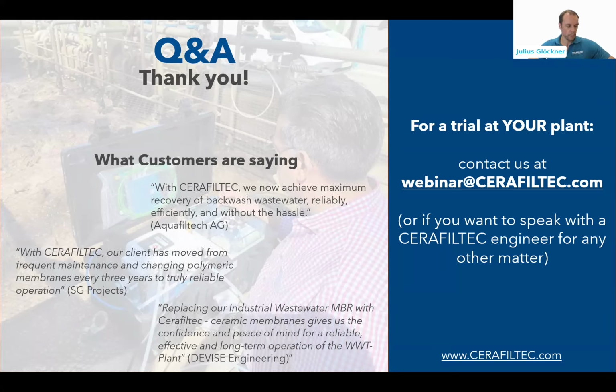I'm sure there are projects running over 20 years. We have experience with a couple of projects that are getting close to it. We have one plant that our team installed 14 years ago. It's actually in Saudi. And I can tell you that the ceramic membranes in this project are exactly today as they were on the day we installed it. There hasn't been a performance decay. I don't think they did a single maintenance on these membranes in the 14 years, and they might operate for another 30 years. So it's hard to predict, but from all signals, indications and performance we see, the ceramic membranes might far outlast the 20 years.